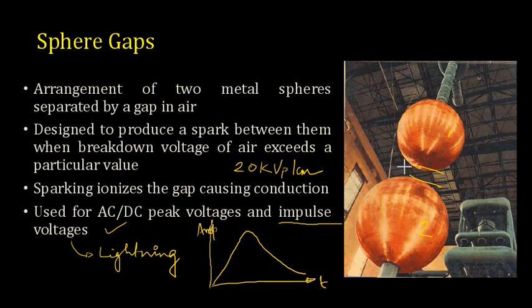The principle of sphere gap is very simple. You apply the voltage across the sphere gap. Once a breakdown occurs, the gap will be ionized, and the spark ionizing the air gap causes a reduction in resistance and aids conduction. Once it starts conducting, the voltage drops drastically, because before conduction it is open circuited, and once it is conducting, it is short circuited. So the voltage across this spark drops drastically. At that moment we can measure. Just before that, the voltage is recorded just before the breakdown, and that voltage gives the breakdown voltage for that particular diameter of the sphere and that particular gap distance.